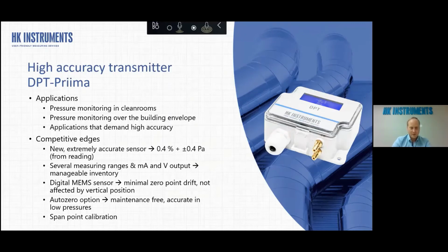Then this is basically almost the same as the one I showed before, the DPTR8, but this is a new model in which we have updated the sensor to be more precise, to focus on clean room applications and all the other applications which require higher accuracy, such as building envelope measurement. You can see the accuracy rate there. It's ±0.4 Pascal, and that's from the reading, not from the full scale. So basically, I have calculated that the accuracy is about 0.5 Pascal within the range of ±50 Pascal. So that should be adequate to be used in clean room applications.